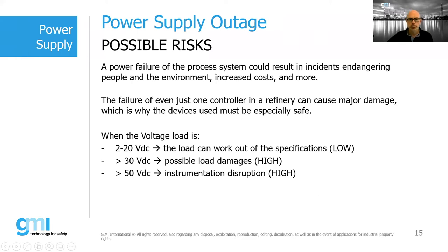But what are the dangerous conditions for a power supply system? Well, mainly there are two dangerous conditions. The first one is an undefined load voltage in a range between 2 and 20 volts, which must be considered a dangerous failure of our power supply. This is because an incorrectly powered load works or can work out of specification, and this leads to a reduction in load performance that can cause a premature instrument failure. Often we try to avoid this issue using redundancy, but we mistakenly think that two power supplies in parallel are sufficient to make us immune from possible faults in the power supply system.